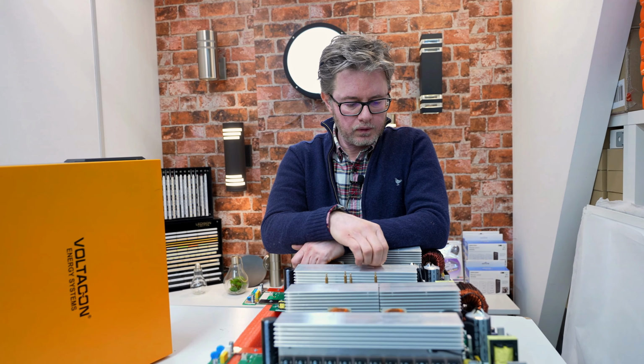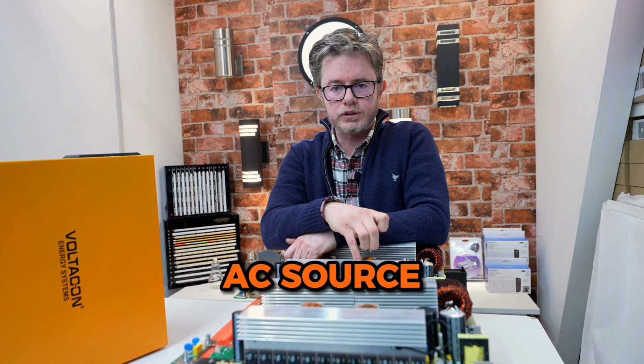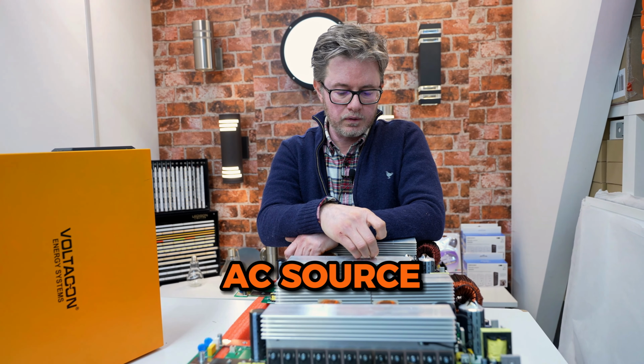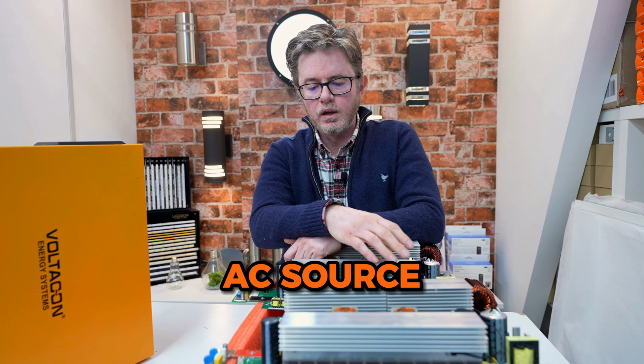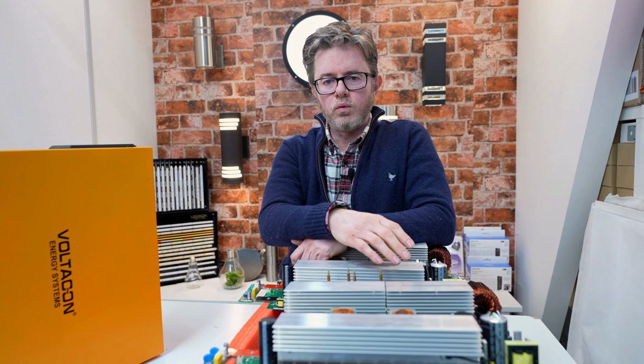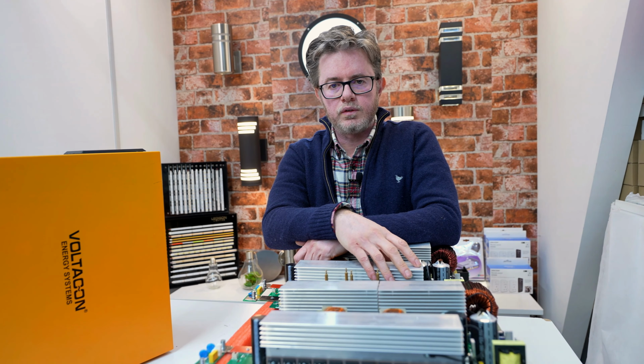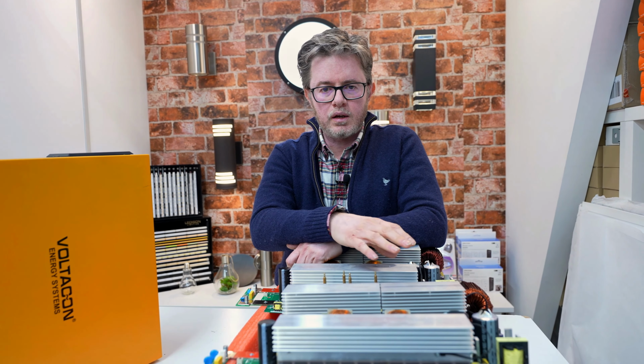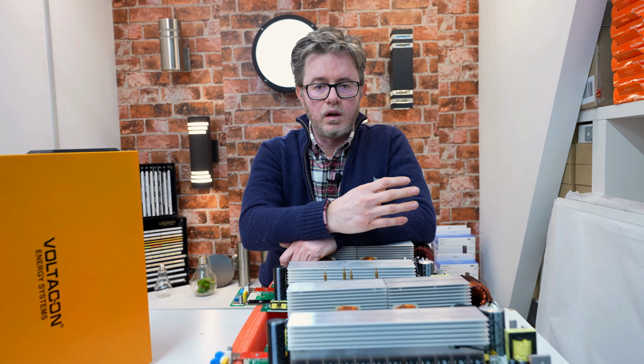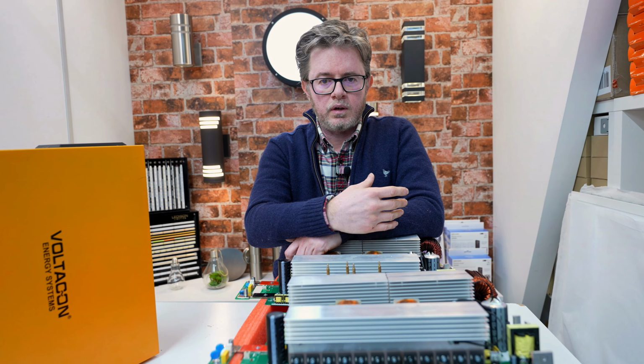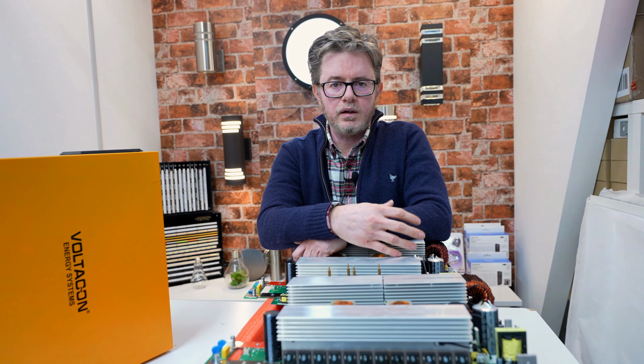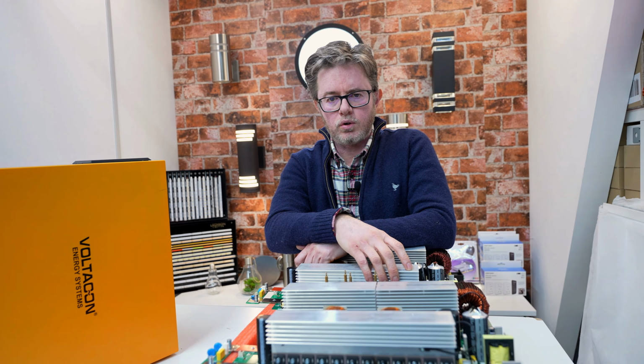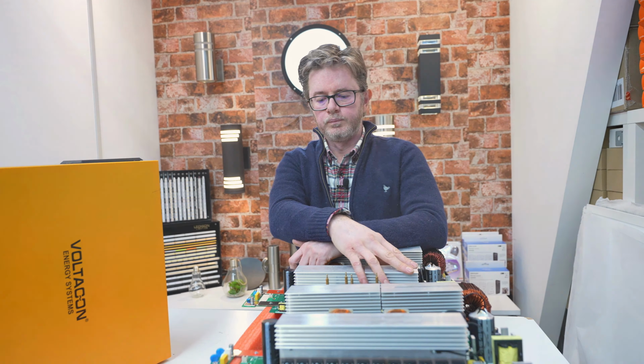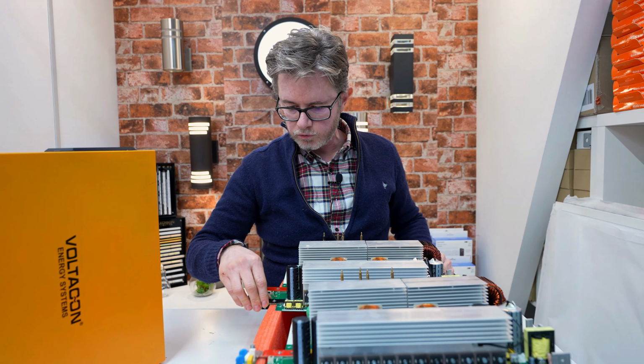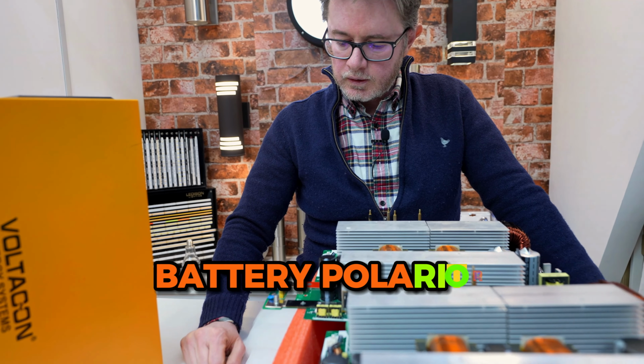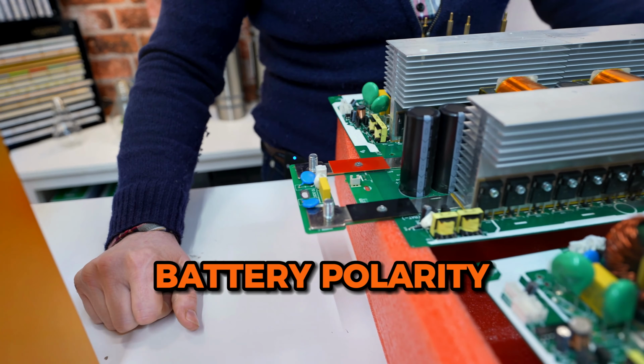The other reason is from the AC source. The AC source can also create the same error 09. If you don't have surge protection or the right varistors on the AC input or the PV input, again, you can blow up the inverter. Especially with generators, the inrush current can be quite high, and this can definitely damage the electronics of the main inverter board. Last but not least, always be careful to check the polarity of the battery terminals.